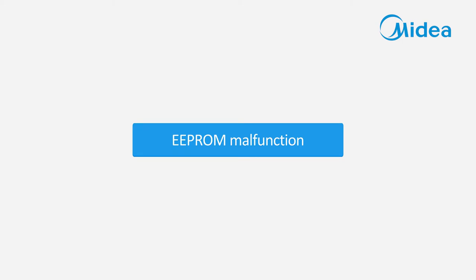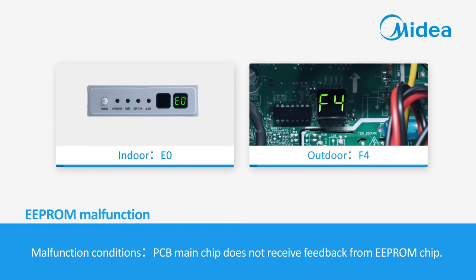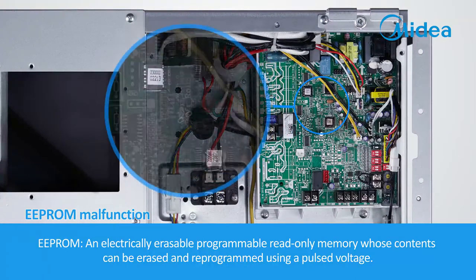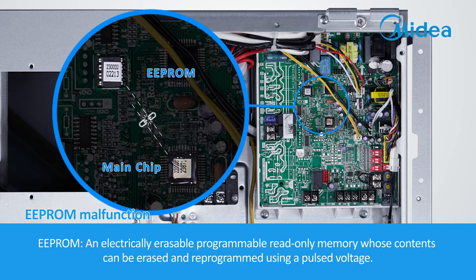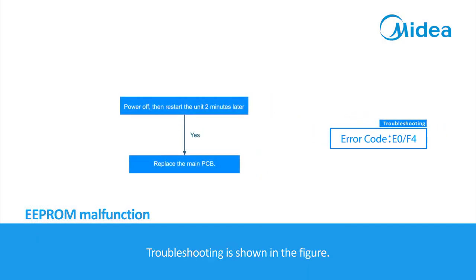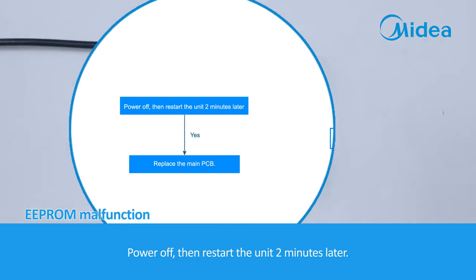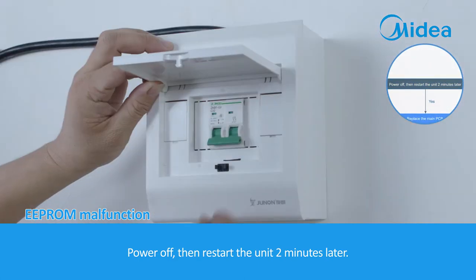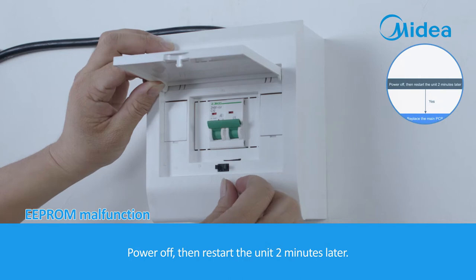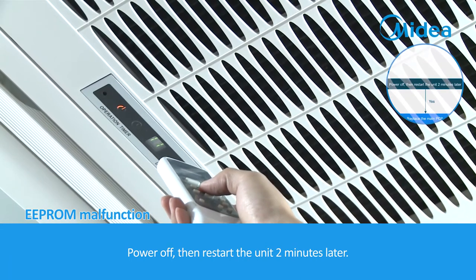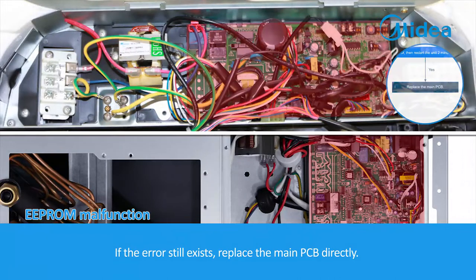EEPROM malfunction. Malfunction condition: the PCB main chip does not receive feedback from the EEPROM chip. EEPROM is an electrically erasable, programmable, read-only memory whose contents can be erased and reprogrammed using a pulsed voltage. Troubleshooting: power off, then restart the unit two minutes later. If the error still exists, replace the main PCB directly.